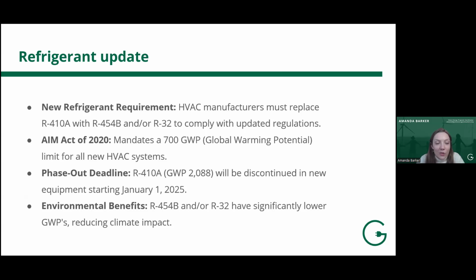In 2020, the AIM Act was passed by Congress, mandating a 700 global warming potential limit for all new HVAC systems. This has caused HVAC manufacturers to replace their current refrigerant, typically R410A, with refrigerants that have lower global warming potential, namely R454B and/or R32, to comply with these new regulations. The phase-out deadline was January 1st of this year, so all new equipment will be built with these lower GWP refrigerants. However, you can still buy equipment already on the market that has the former refrigerant.